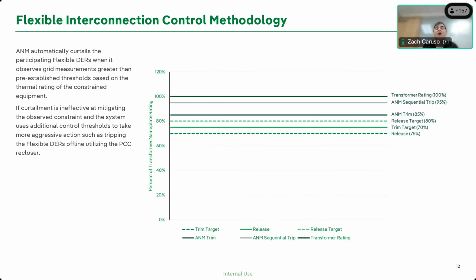And just to give a little bit more context on how ANM works, it's built on this defense in depth or layers of control methodology, where we have a trim threshold. As I said, we're monitoring the current flowing through the bank. When that current goes above a certain limit, in our case 85% of the bank's thermal rating, the system will take action to curtail the PV sites that are part of the flexible scheme, and it will continue to curtail them, trying to maintain them within an operating area, up until that current flow drops to a safe level where it can release all of the capacity back to the DER sites, and they can go back to normal unconstrained operation.